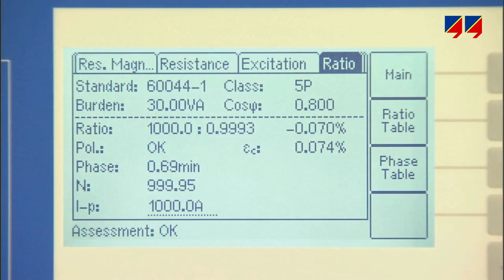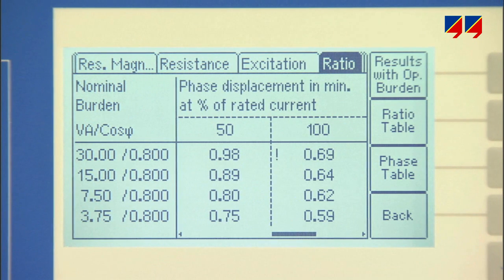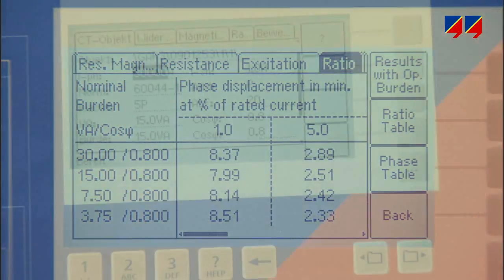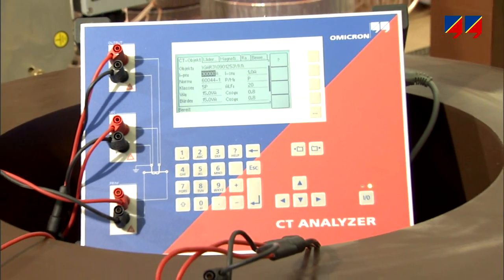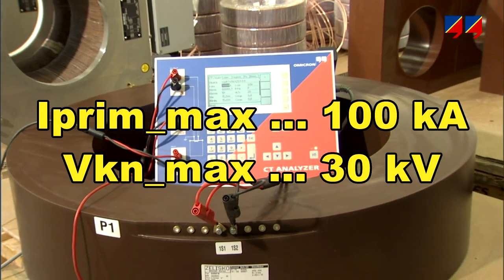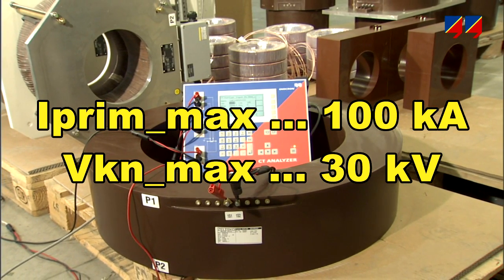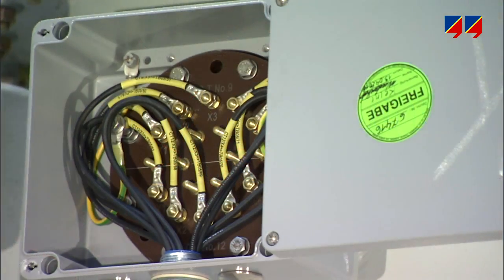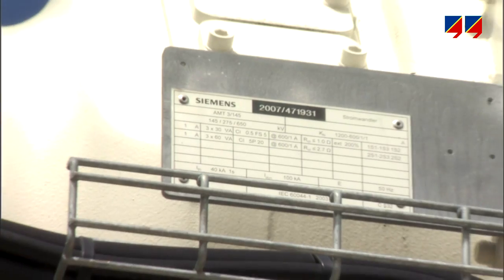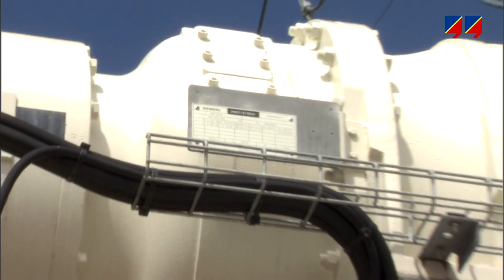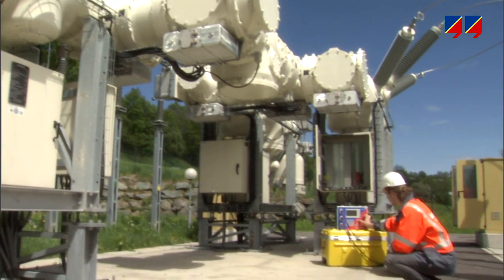Based on these measurements, it determines the accuracy data for all defined current and burden value combinations. Using this approach, all types and sizes of CTs can be tested, even exceptional types with primary currents of up to 100 kiloamps or with knee point voltages of up to 30 kV. It can test any CT, including installations that by conventional methods have been difficult or impossible to test so far, such as CTs in transformer bushings or gas-insulated switchgear.